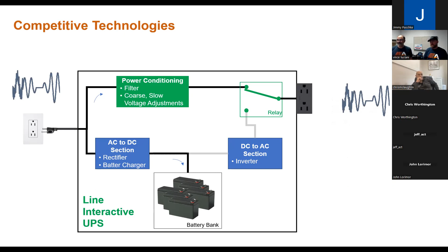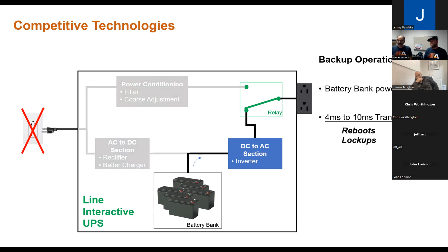During backup, when the power goes away, the batteries take over powering that inverter. However, that relay takes between 4 and 10 milliseconds to switch over. That is the biggest detriment, because depending on the piece of equipment, that 4 to 10 milliseconds can cause a problem, cause a reboot, cause a glitch, or require a reboot. It may just lock it up to the point where you have to physically go out there and unplug the thing.